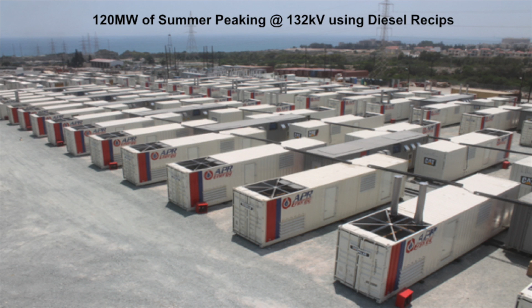Being able to come in and put in 120 meg at 132 kV on the grid in a matter of weeks solved the problem. Summer peaking here in the US is the same thing. We've got grid capacity constraints, so we come in putting temporary distribution generators into substations, put 5 or 6 megawatts in to take up that area and free up the main high voltage transmission lines, taking the rural load off the grid.